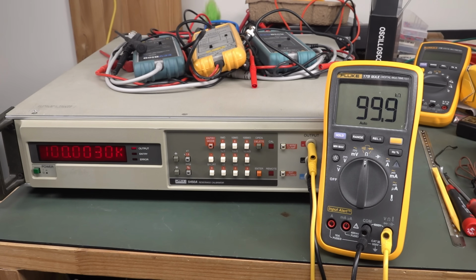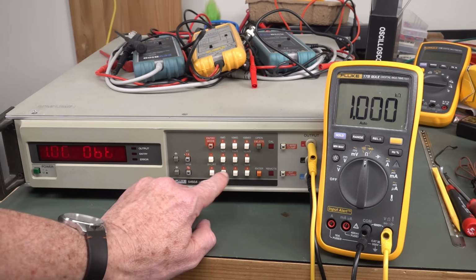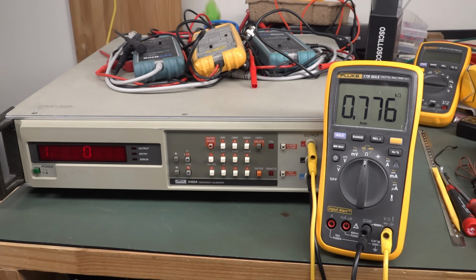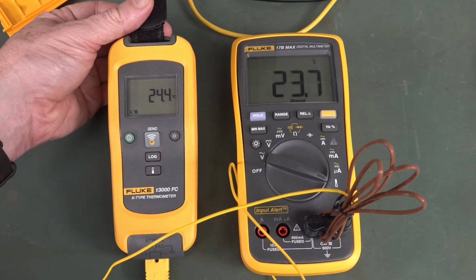It's creeping up there. There you go. 10K. Yeah, crept up there. 1K. Yeah, not too shabby. 100 ohms. Now we're getting down to lead contact resistance, of course. That's probably it for the leads. We don't really need to go any lower than that because it doesn't have a lower range. That's a winner chicken dinner. Temperature seems good enough for Australia.